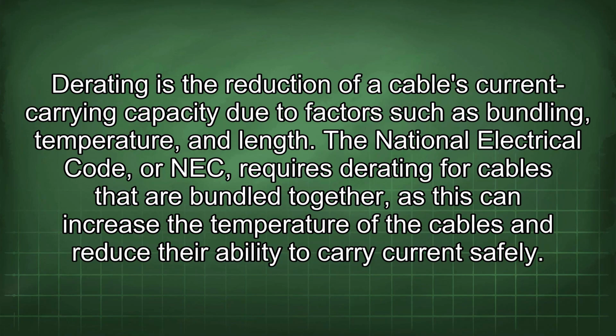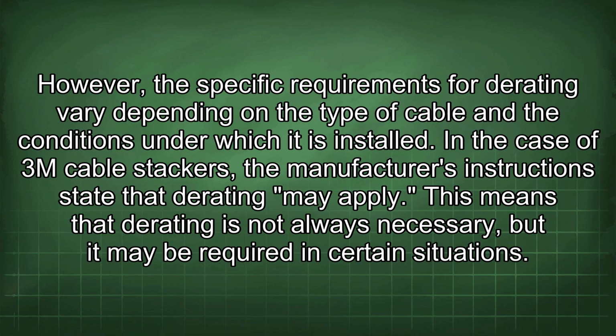Derating is the reduction of a cable's current carrying capacity due to factors such as bundling, temperature, and length. The National Electrical Code, or NEC, requires derating for cables that are bundled together, as this can increase the temperature of the cables and reduce their ability to carry current safely. However, the specific requirements for derating vary depending on the type of cable and the conditions under which it is installed. In the case of 3M cable stackers, the manufacturer's instructions state that derating may apply. This means that derating is not always necessary, but it may be required in certain situations.